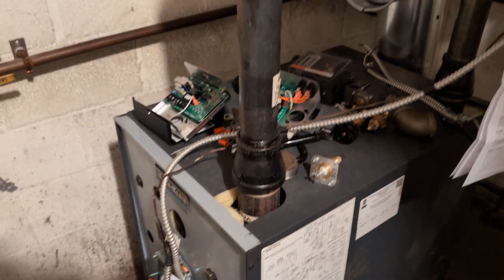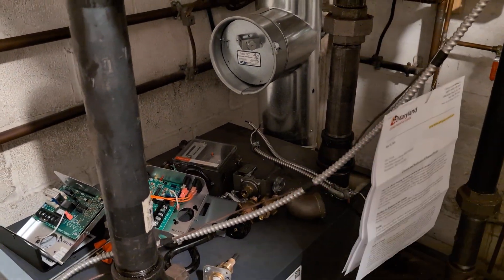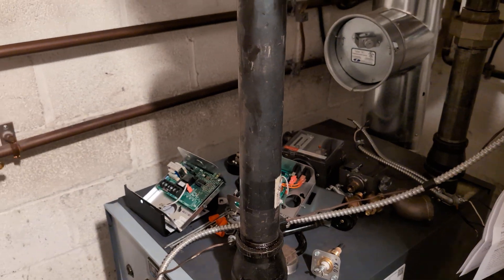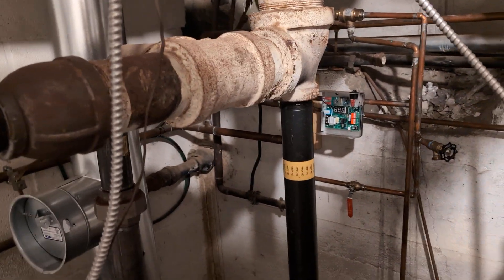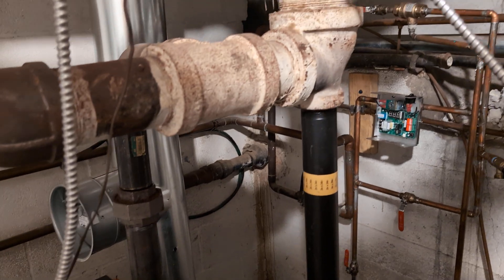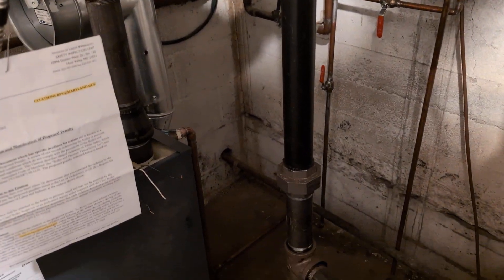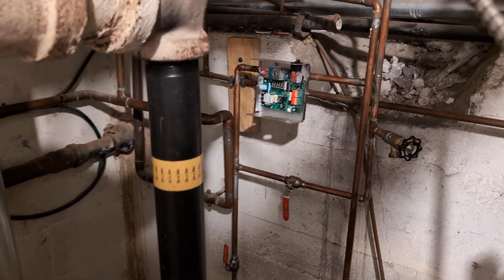The other issue is that this is an SG07, and the instructions call for the two outlets to be two-and-a-half inch. They reduced it down to two inch and tied it into the existing header. You can quibble about the tee there, but sometimes you have to do what you have to do.